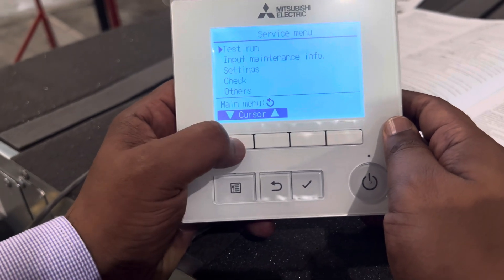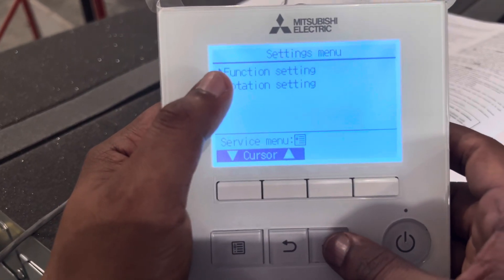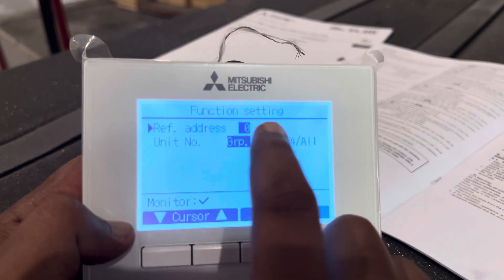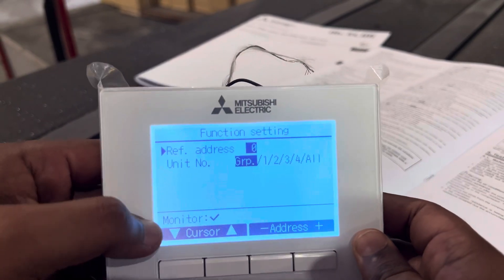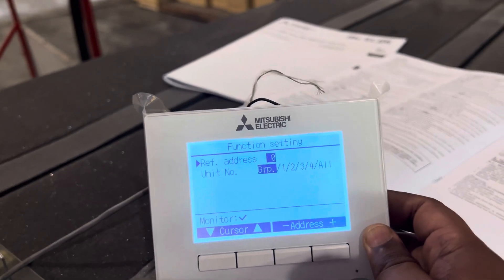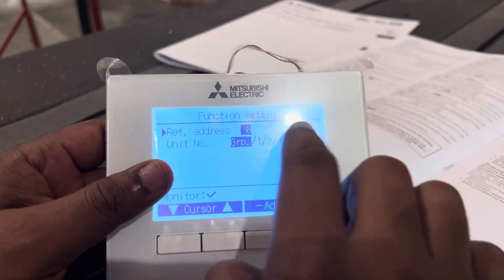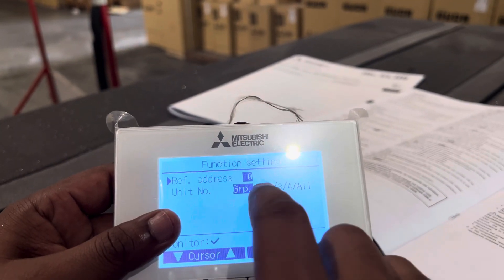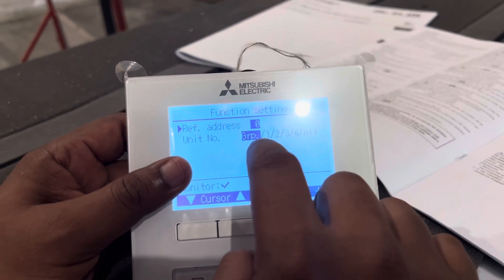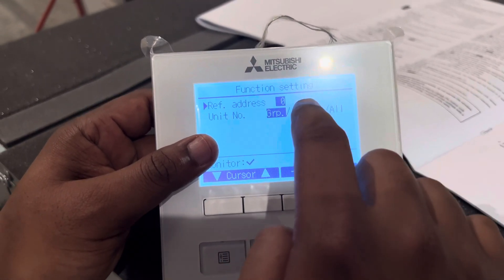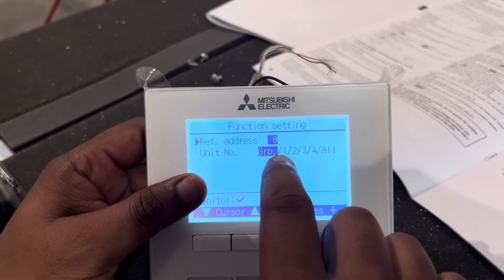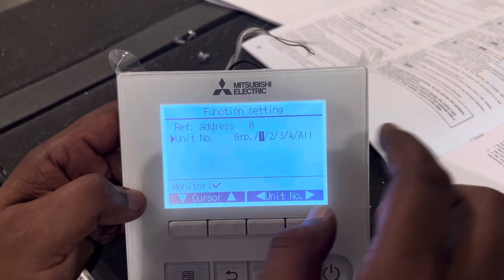Press enter, scroll down, and come to settings. Enter the function setting. Here you'll see the refrigerant address — by default from the factory it is 0, but in case someone has changed it, it may be 1, 2, or 3. Set it to whatever the refrigerant address is. For this model it is 0, which is the factory default. Then set the unit number to 1 — make sure you select unit number 1 when changing the static pressure. Set the refrigerant address and unit number, then confirm.